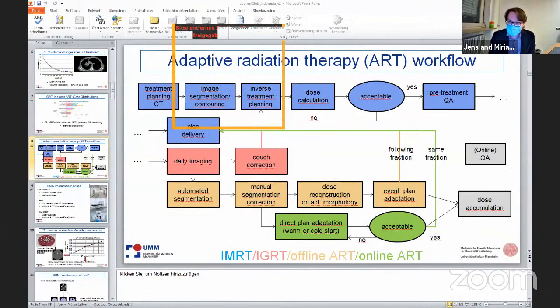Good. So now let's go through the actual process of radiation therapy, and let's think what would need to be changed in order to establish an adaptive workflow. I'm referring to the normal 3D conformal radiation treatment planning workflow, where we perform a treatment planning CT, take this CT and perform an image segmentation or contouring process of the target volume and of the organs at risk. We would then go into the step of inverse treatment planning in the case of intensity modulated radiation therapy. Once we have set all the specific constraints, we would perform a dose calculation. And this would be one loop as long as there needs to be improvement. Afterwards, once the plan is acceptable, we will perform our quality assurance and perform the actual treatment. So that is the standard workflow.